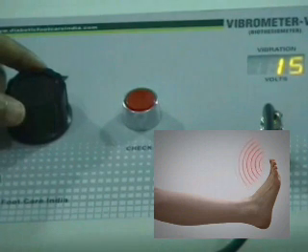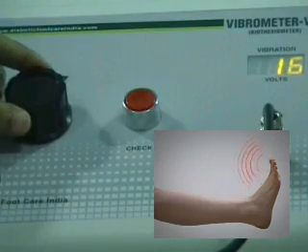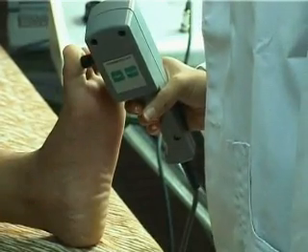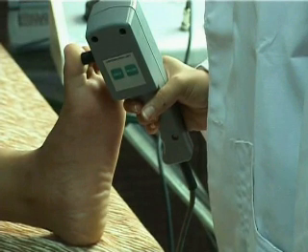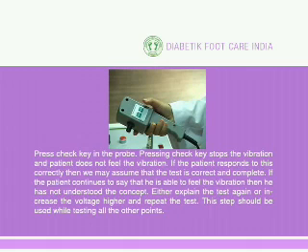As the voltage increases, the strength of the vibration also increases. Ask the patient if they feel the vibration. As soon as the patient responds, press the check key on the probe. Pressing the check key stops the vibration and the patient should no longer feel it. If the patient responds correctly, we may assume that the test is correct and complete.